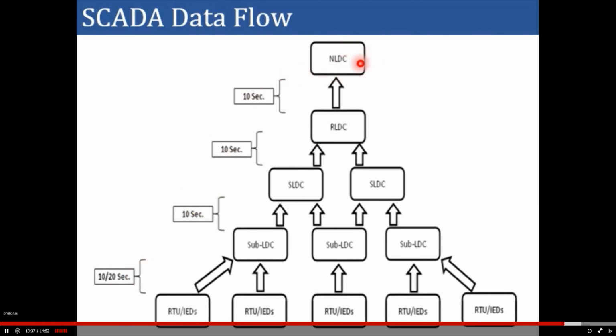So at the NLDC level, if an event occurs, the effect is seen only after about 1 minute. This is a major challenge in the conventional way of SCADA data communication, because on 30th and 31st July 2012 we had a blackout, and the transition from a healthy to a blackout state happened in just 3.5 seconds. So you can understand that if you cannot visualize changes in the power system network within a small fraction of time, it becomes very difficult to avoid blackouts.